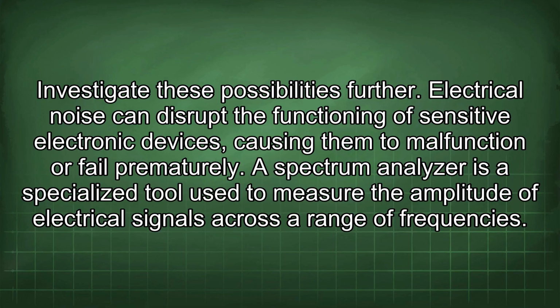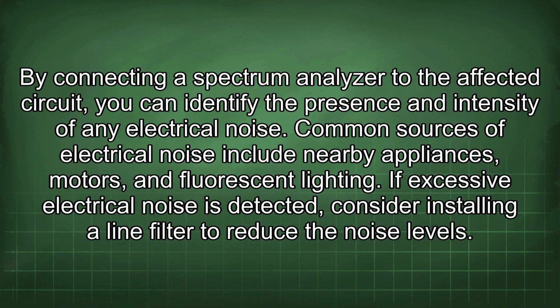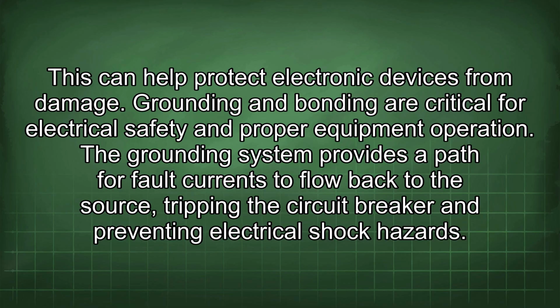Investigate these possibilities further. Electrical noise can disrupt the functioning of sensitive electronic devices, causing them to malfunction or fail prematurely. A spectrum analyzer is a specialized tool used to measure the amplitude of electrical signals across a range of frequencies. By connecting a spectrum analyzer to the affected circuit, you can identify the presence and intensity of any electrical noise. Common sources of electrical noise include nearby appliances, motors, and fluorescent lighting. If excessive electrical noise is detected, consider installing a line filter to reduce the noise levels. This can help protect electronic devices from damage.